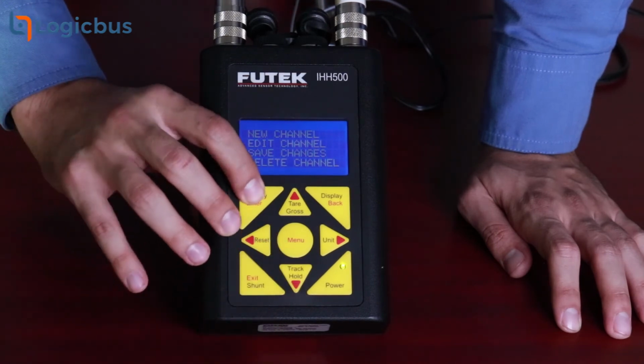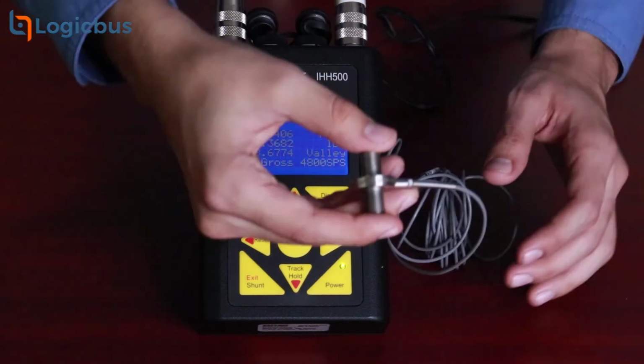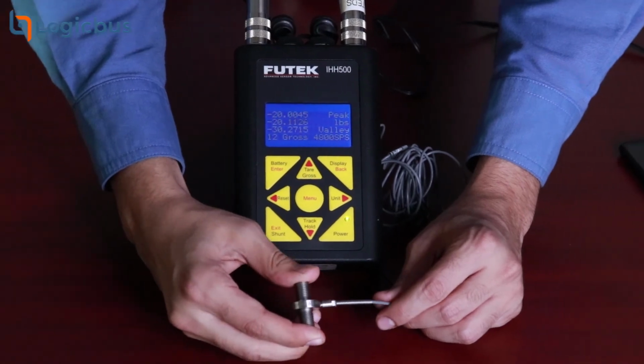After we set this up, we're ready to go, so we'll have to hit the Save Changes option. If you see a little blip on the zero, it's because it didn't run a zero load calibration, but if you did run this test, you should be good to go. With these simple steps, our device is now ready to go.